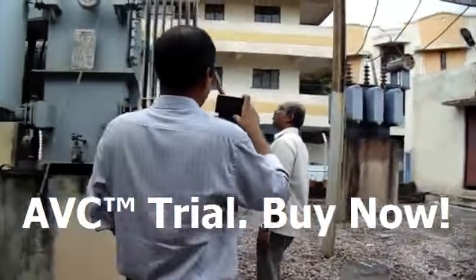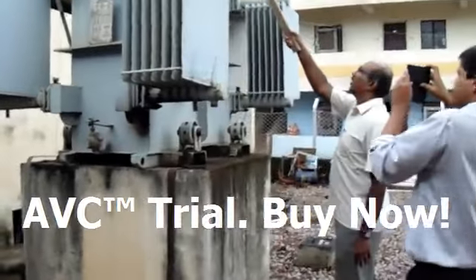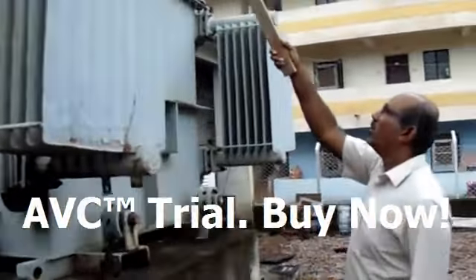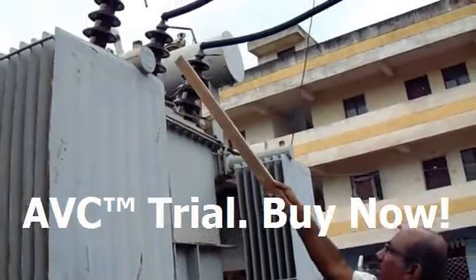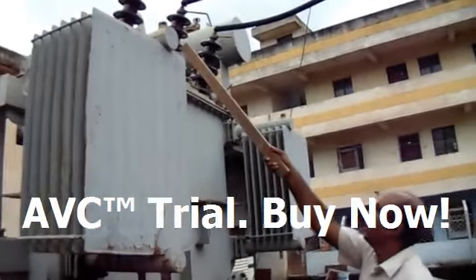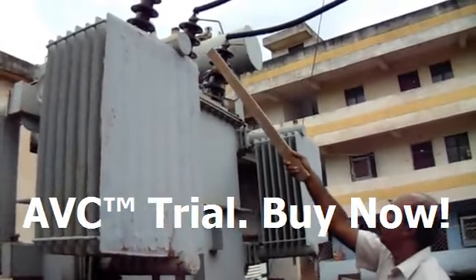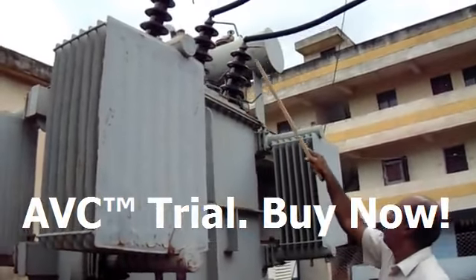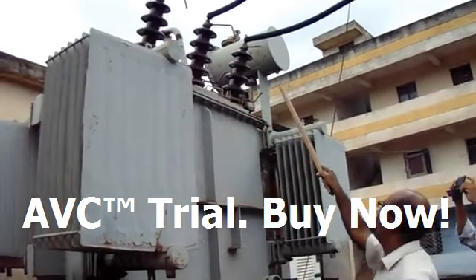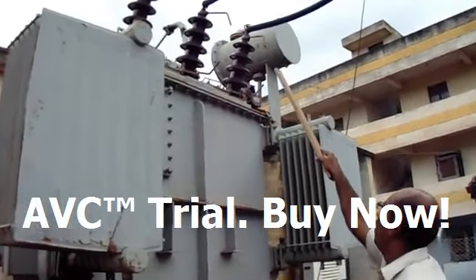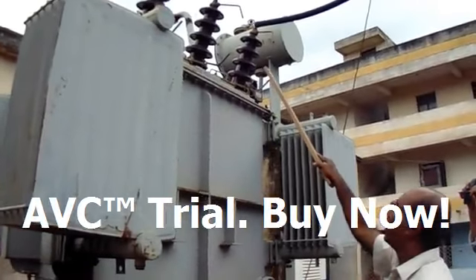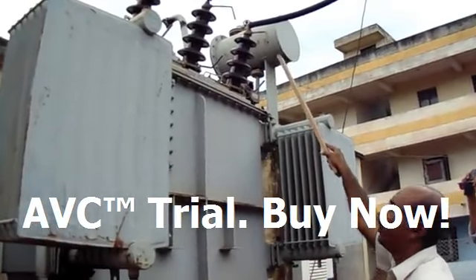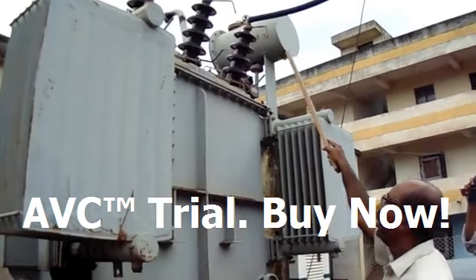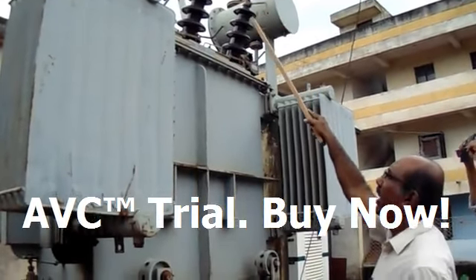HT side, you see that the overhead wires are directly terminated to this bushing, which is known as the HT bushing, and you can see that there are two rods, and these rods are known as the arcing rods. The function of these rods is to protect the transformer from any surge, whether it's a lightning surge or a switching surge. Mainly it is for the lightning surge.